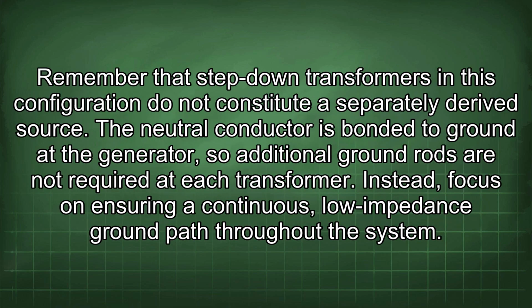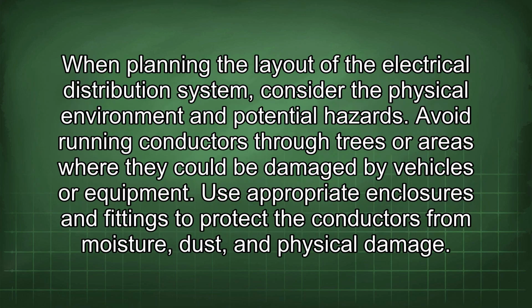Remember that step-down transformers in this configuration do not constitute a separately derived source. The neutral conductor is bonded to ground at the generator, so additional ground rods are not required at each transformer. Instead, focus on ensuring a continuous, low-impedance ground path throughout the system. When planning the layout of the electrical distribution system, consider the physical environment and potential hazards. Avoid running conductors through trees or areas where they could be damaged by vehicles or equipment.